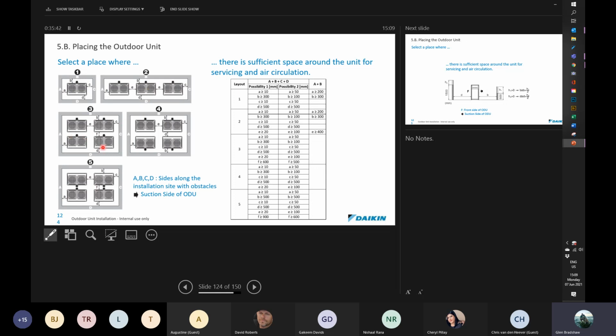Different options for plant areas. For instance, here you'll see that the arrow denotes the air intake on the condensers. So here we need 2 service aisles, and those distances would obviously take up more space. What we can do is rotate them around and create 1 service aisle. So we need to be a bit more creative. In some instances, we can create 1 aisle for the air.